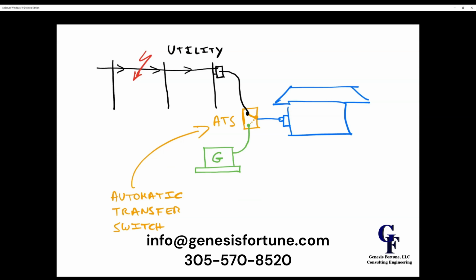If the utility power gets interrupted, the ATS or automatic transfer switch will go to the position below and take power from the standby generator. Once that happens, the standby generator has its logic to start running and provide power. So the house can take power from either of the two, but obviously not both at the same time.